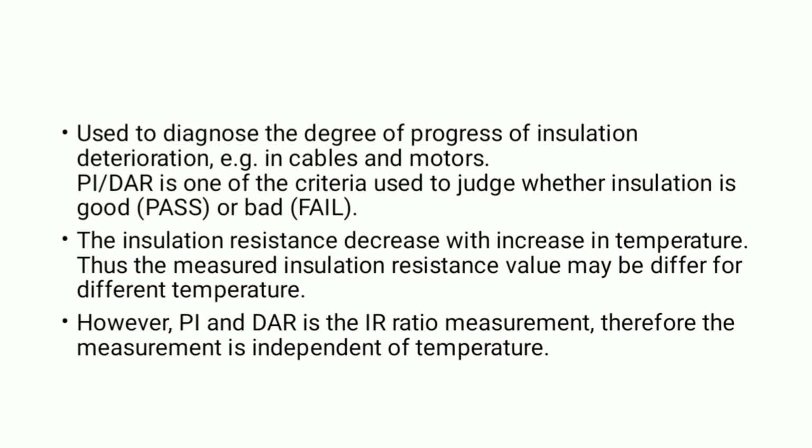In DAR and PI we are taking the ratio of the insulation resistance, so both are unitless. As we are taking the ratio of two resistances, they are independent of external factors like temperature, dirt, moisture, etc.